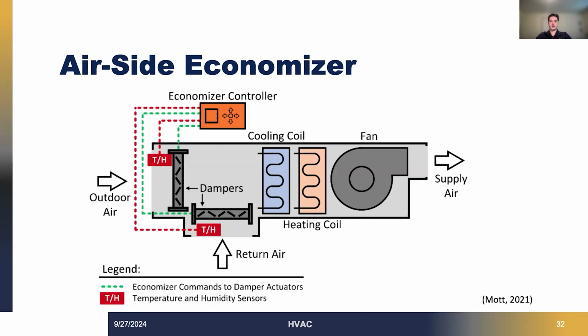Here's a diagram of an airside economizer. It's important to note that these units filter outdoor air and facilitate the mixing of outdoor air with return air to achieve the desired indoor air temperature. The economizer controller serves as the system's brain, continuously measuring the temperature of the outdoor air to determine whether it can be utilized for cooling. This intelligent management ensures optimal energy efficiency while maintaining comfort within the building. It is important to note that it is all filtered, so it's not just letting in outdoor air. There's always an air filter on this airside economizer.